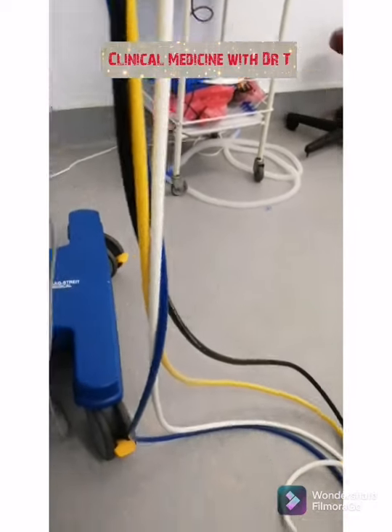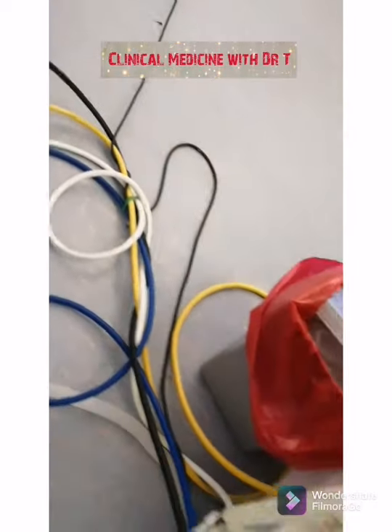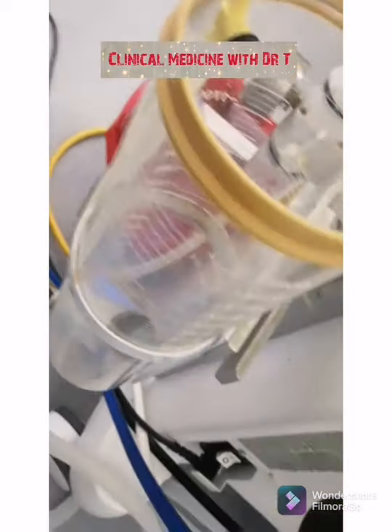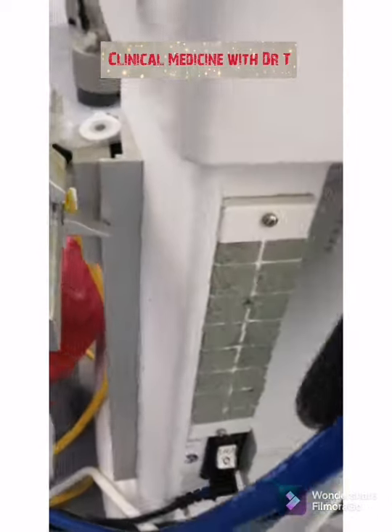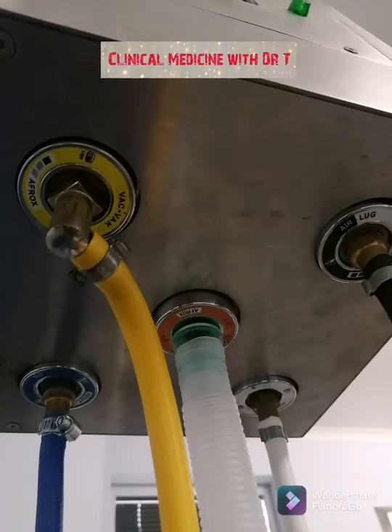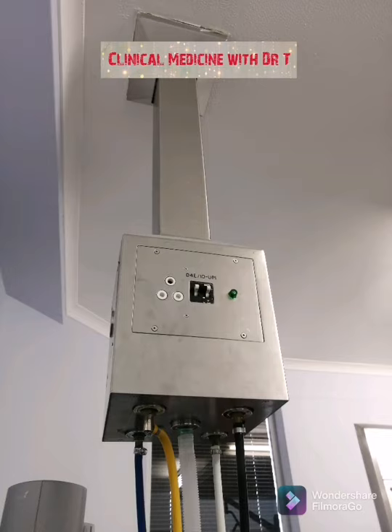And then there are pipes that emanate from there to different wards, to different theaters from the same supply. So oxygen, nitrous, air, they are all stored in the central supply. That's why you always have something that is overhanging, or that is just floating, but not really floating.